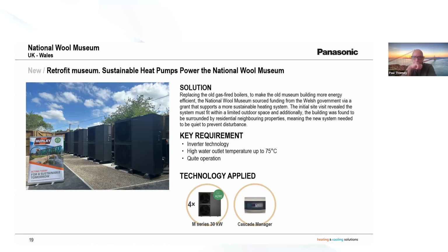This is pipes in sequence, connected with Modbus, with buffers in the plant room. It's a fantastic install that Hurley's did, and it was great to play a key role in the initial setup, making sure it was done to schematics and the wiring, etc., then configured. It's controlled by a cascade manager, which is now externally controlled by BMS - great for a commercial solution that wants external control also. I really enjoyed participating in this project.